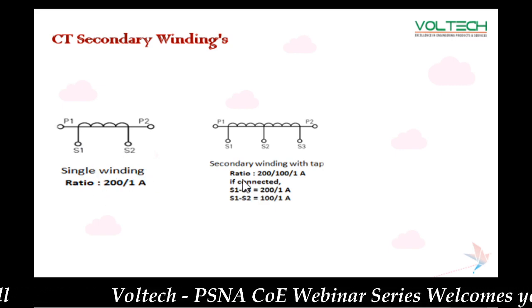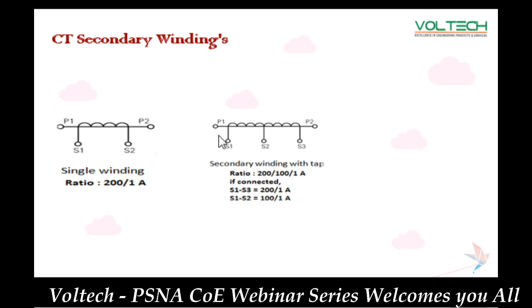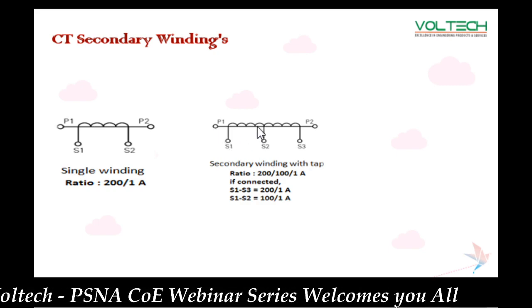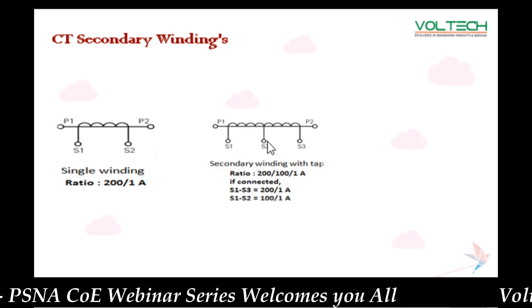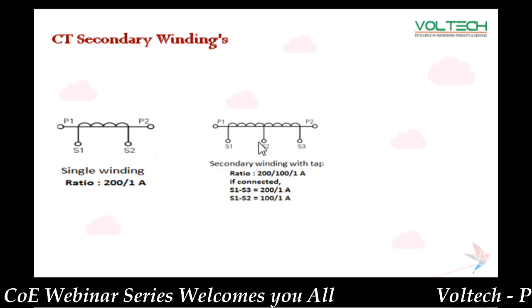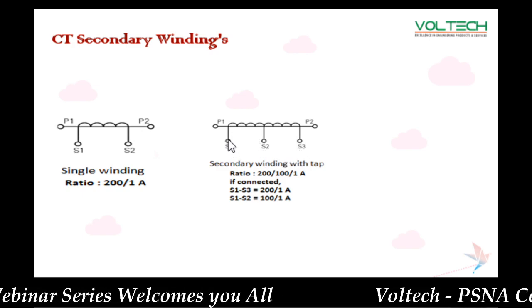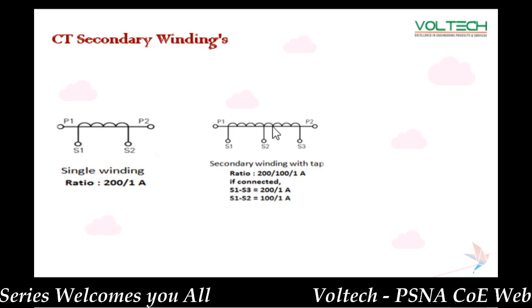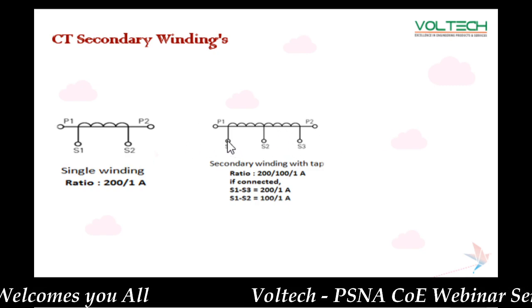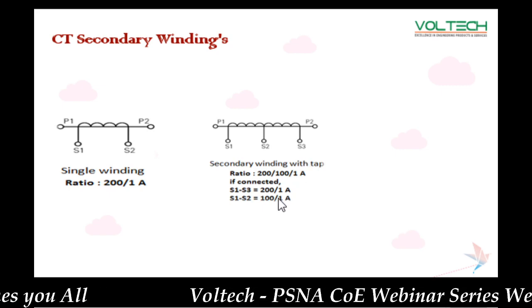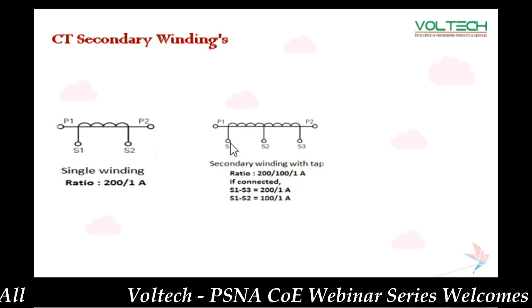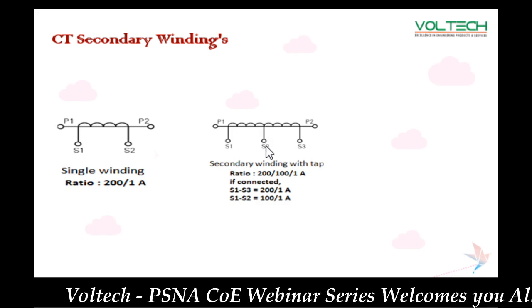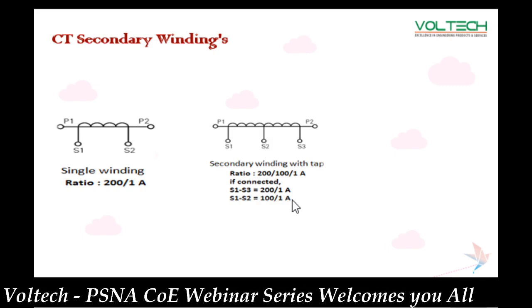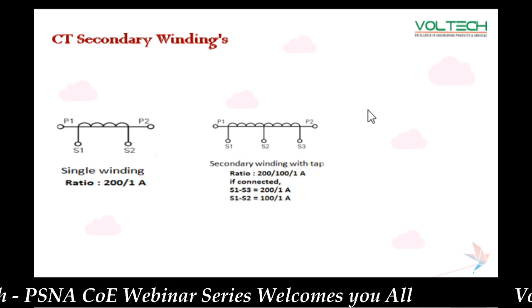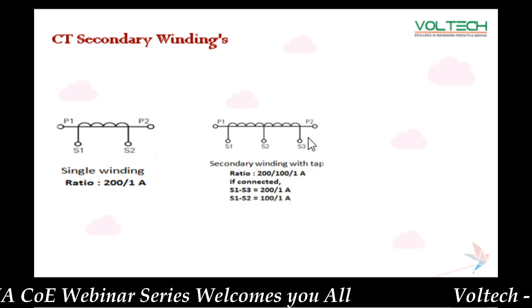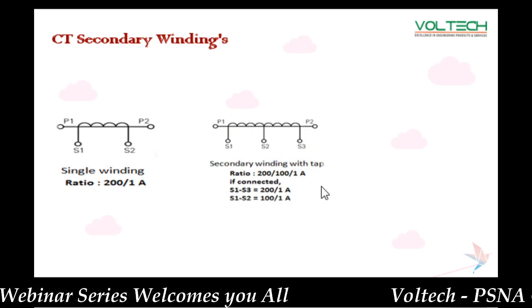But here it is the same type of winding, with one tap in between S1, S2 and S3. Here we can measure the same 200 ampere. We make one more tap here. S1 to S3, if you measure, you will get 200 ampere. S1 to S2, being half of the winding, you will get 100 ampere. So depending on our application, we can use this type of CT winding.